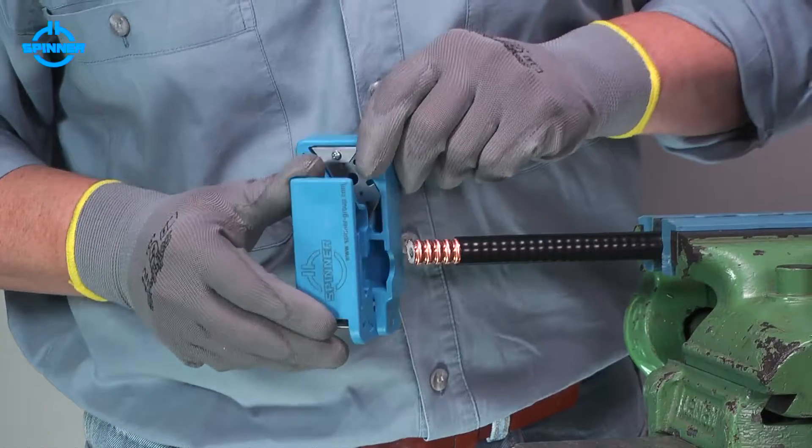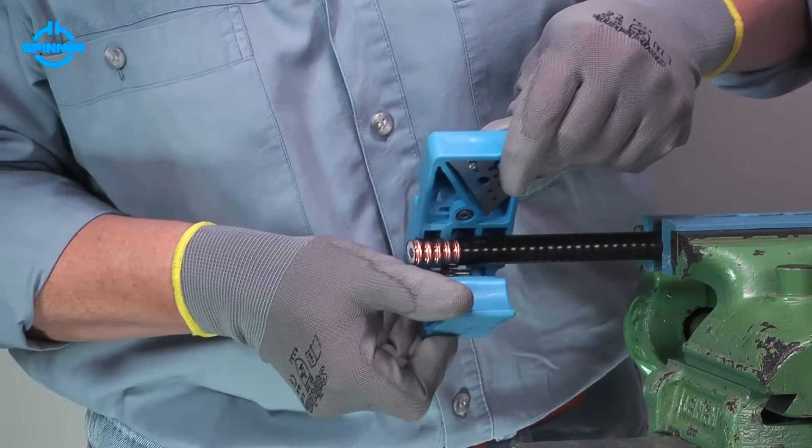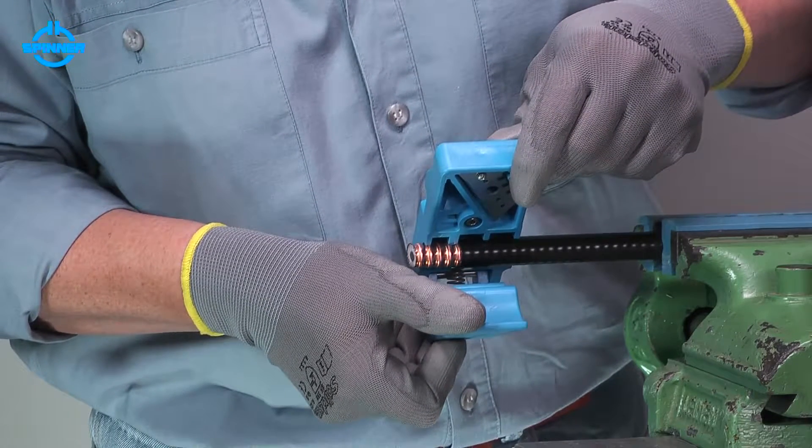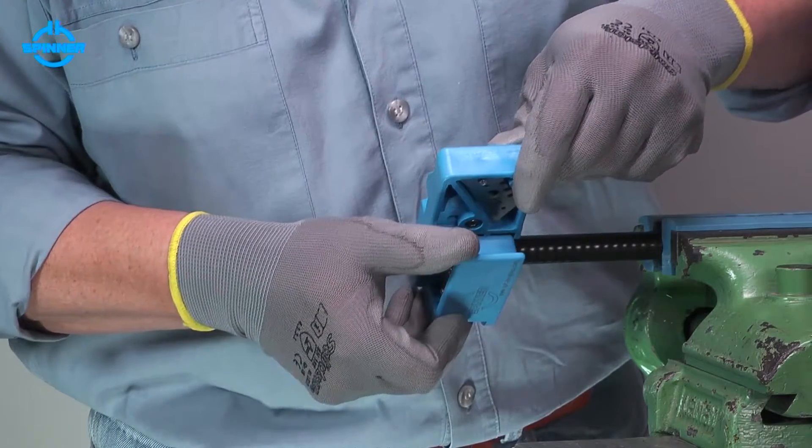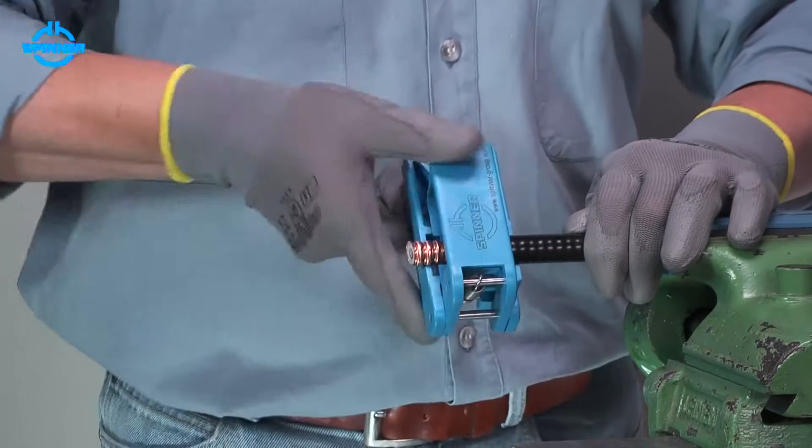Place the collet guide of the trimming tool in the corrugation nearest to the trimmed jacket. Close the tool gently and rotate clockwise until the blade has cut the outer conductor and foam.